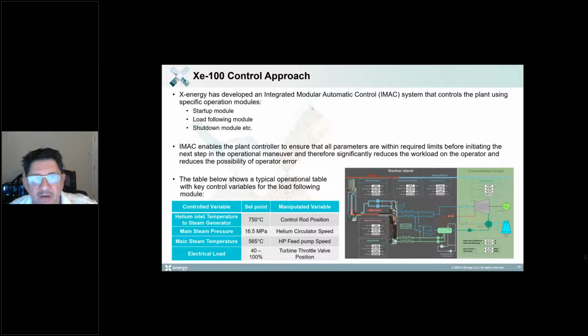We've developed our own integrated modular automatic control called IMAC that uses control modules. Typically, we've got a startup module, a load following module, a shutdown module, maintenance modules, and within those plant states there are very set parameters that the plant cannot move out of.